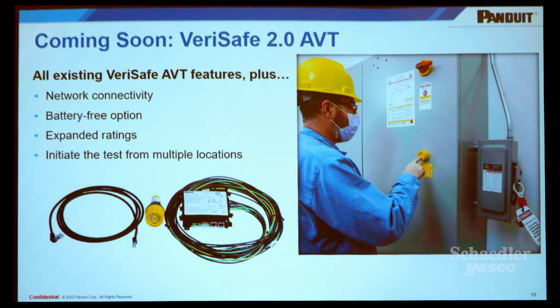It has network modules, so you can actually export all the data from it. So not only when the tests occurred, whether they passed or failed, but it also does some voltage monitoring. So you can measure phase to phase, phase to ground, RMS, and also peak voltages. And then you can collect all that data, and we have the add-on profiles for Rockwell controllers and all that integration. You can also now hook up 2 indicator modules per test point. So some people want 2 areas to test. So if you think of equipment inside of a cage, maybe you want a test button outside the cage and then one at the panel door as well. That's a good example of where you'd have 2 indicator modules.